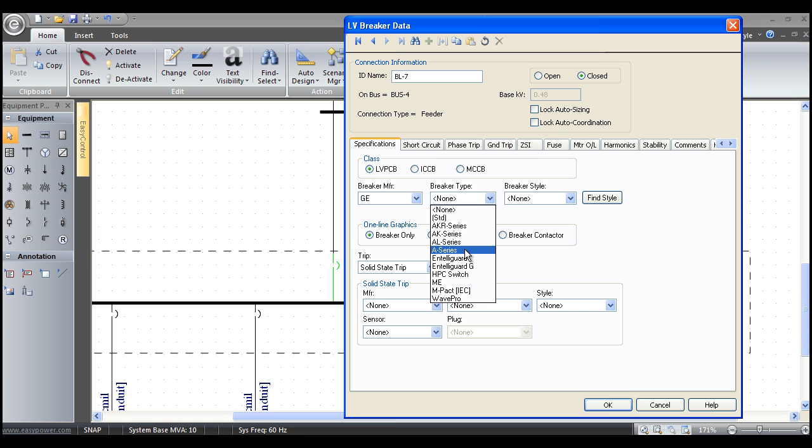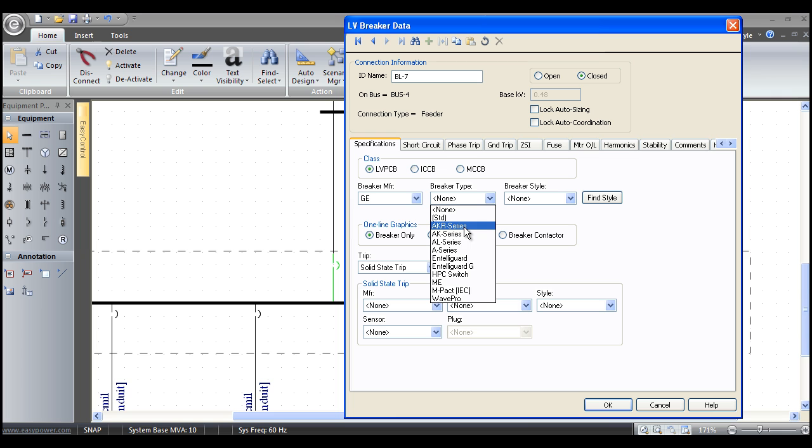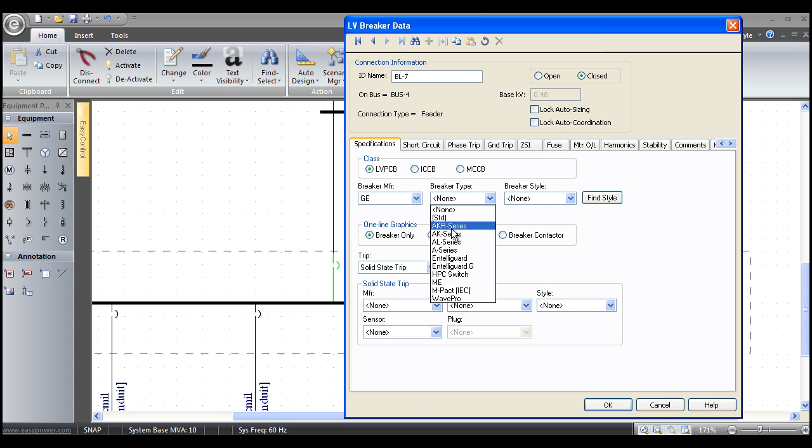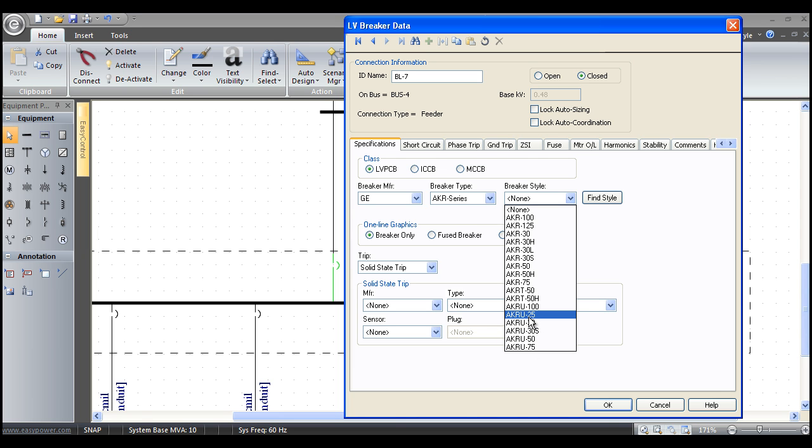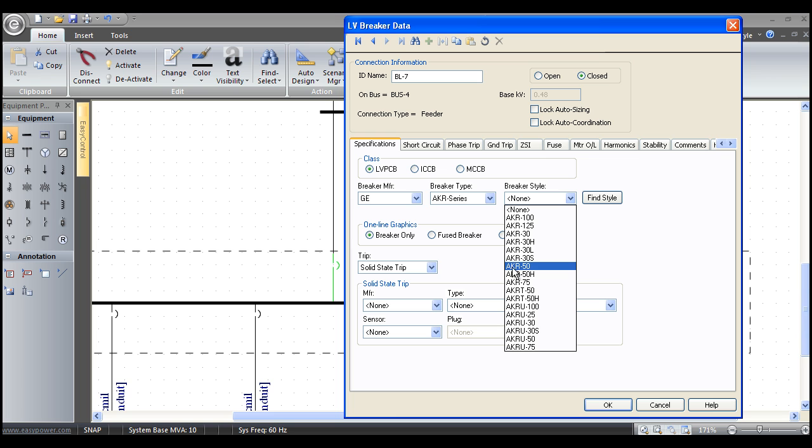If I pick something like GE and then go to the breaker type, it will show me all the different low voltage power circuit breakers GE has ever made. From the 1940 A series, the 1950 ALs, the 1960 and 70 AKs, the 1980 and 90 AKRs, their new Entelliguards and Wave Pros, their IEC MPACs. Let's say I pick an AKR series, it will then give me all the different styles. This is what I really care about is the style of breaker. Here's all the AKRUs, these are the fuse combination, AKRTs, the high capacity Hs, the Ss and the Ls, they're all here. If I pick something like an AKR50, watch what happens when I select it.